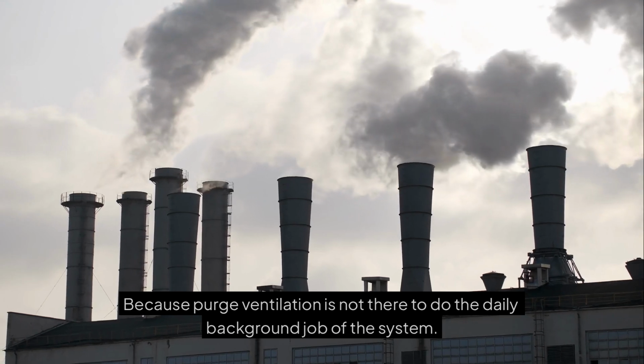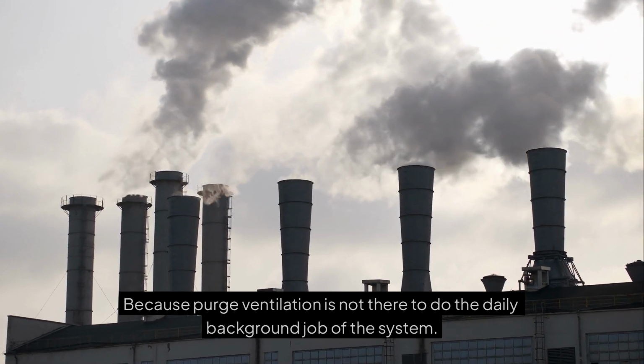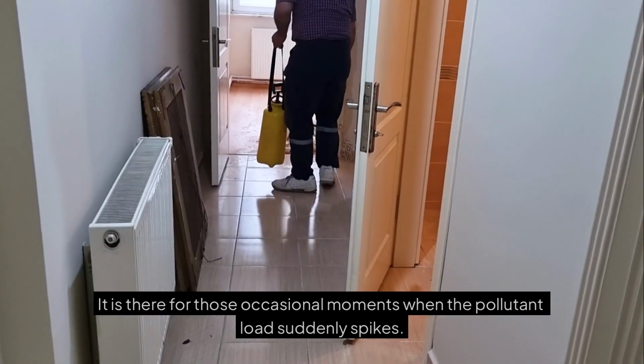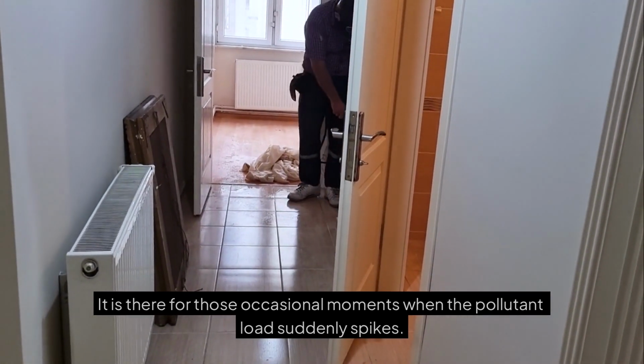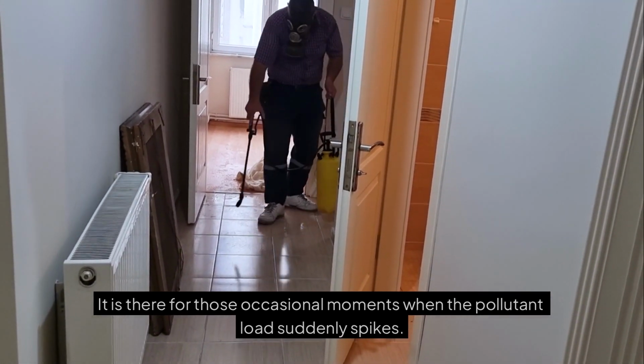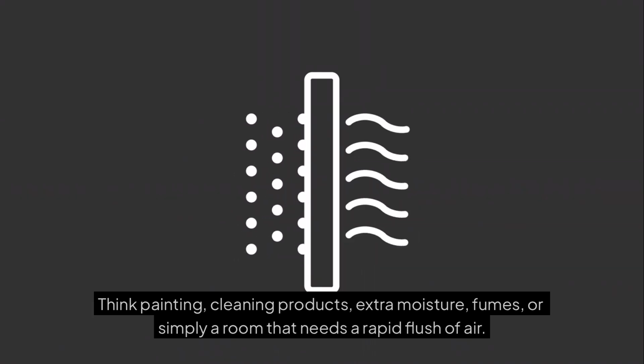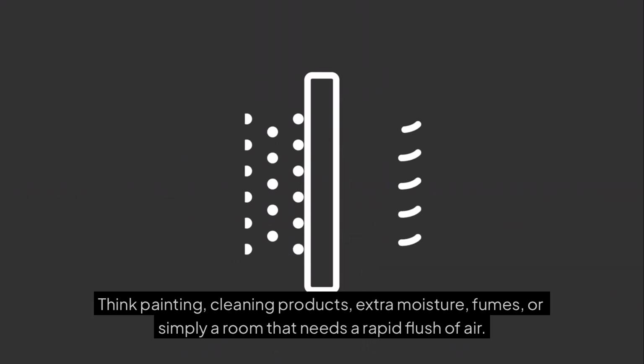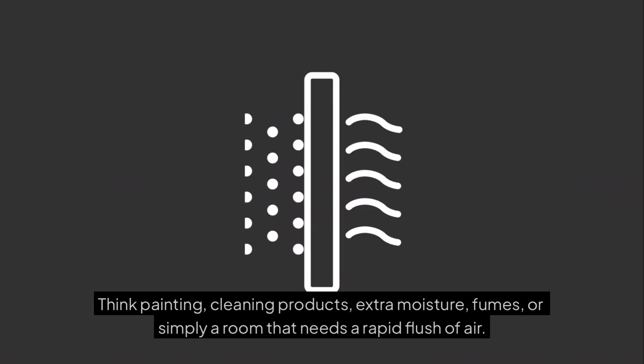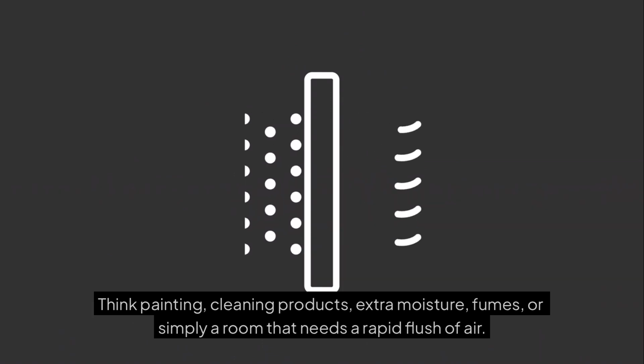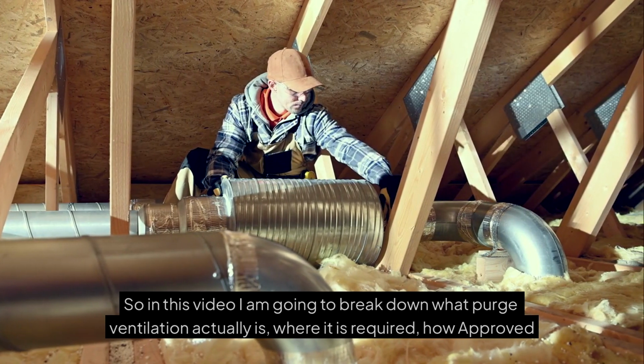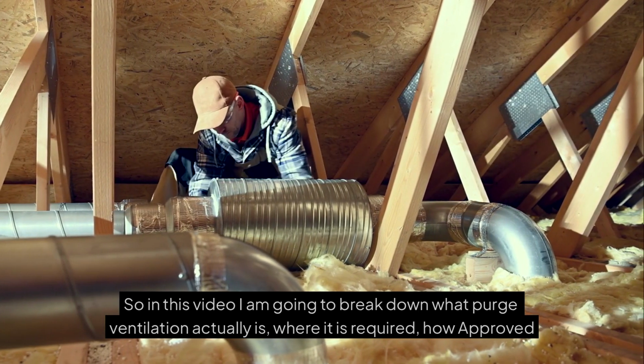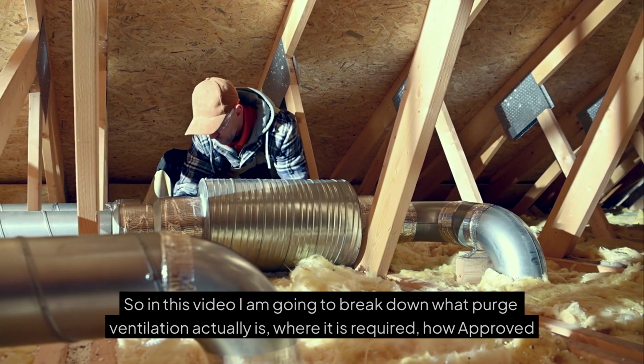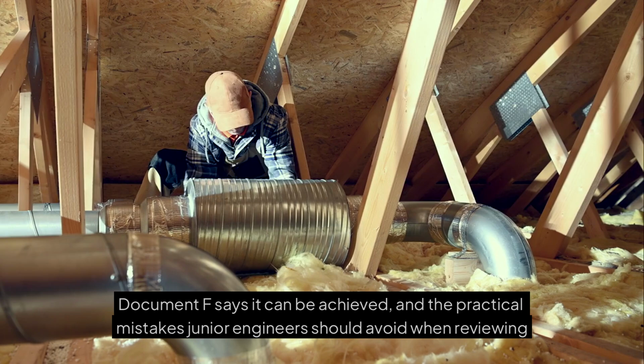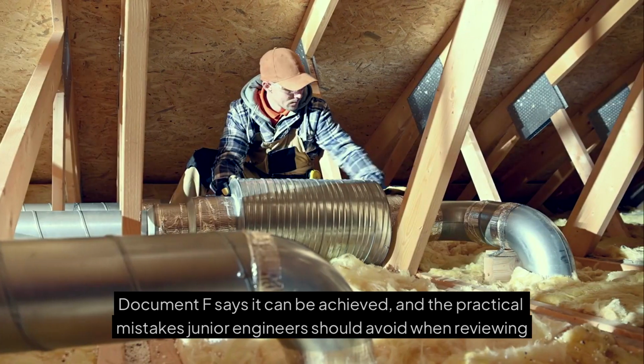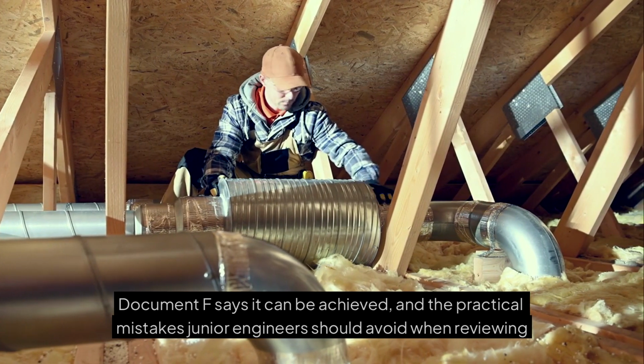Because purge ventilation is not there to do the daily background job of the system. It is there for those occasional moments when the pollutant load suddenly spikes. Think painting, cleaning products, extra moisture, fumes, or simply a room that needs a rapid flush of air. So in this video, I am going to break down what purge ventilation actually is, where it is required, how Approved Document F says it can be achieved, and the practical mistakes junior engineers should avoid when reviewing drawings or layouts.